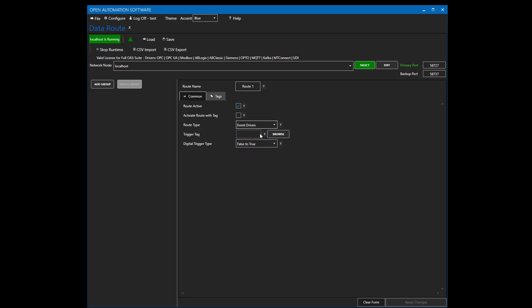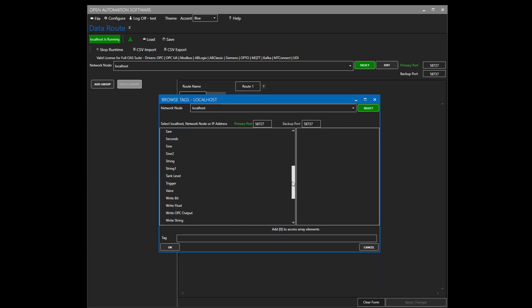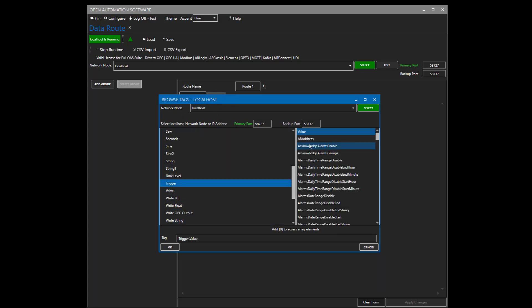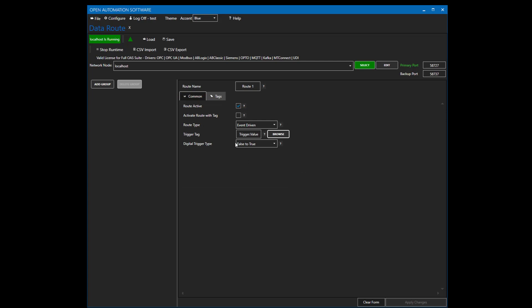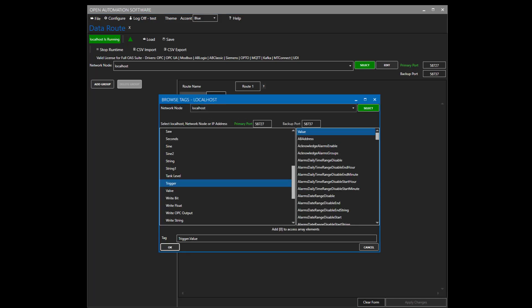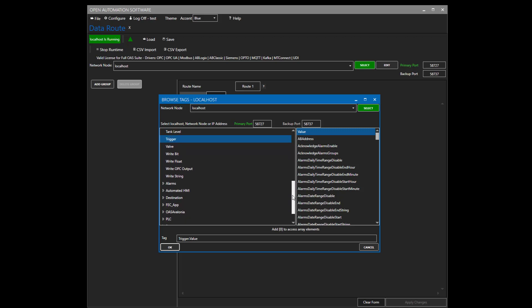I'm going to browse for a tag already in the system called trigger and use the value variable of that tag. You can use any Boolean variable of any local or remote tag. Notice it supports networking as well — the trigger or the values you want to write to or read from can be coming from remote OAS engines, provided you have an active network connection to those remote OAS engines. Now that we've determined how to trigger the data route, we'll use the Tags tab to define what we write to and what is the source of the value to pass along.